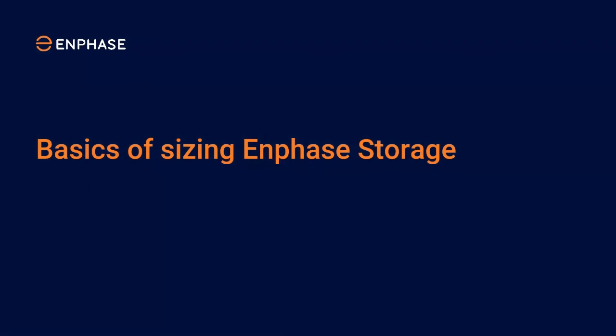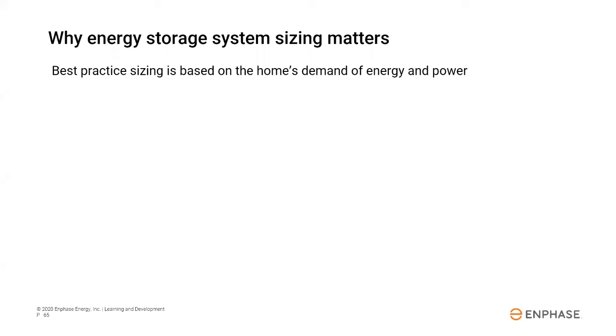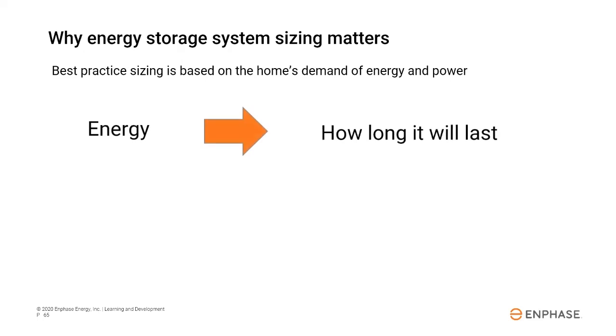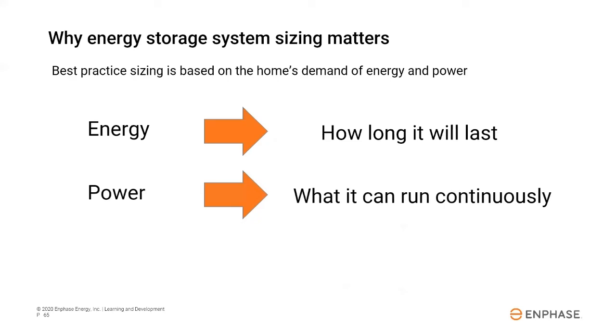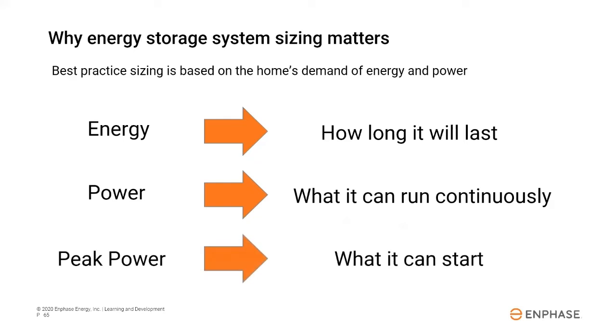Okay, now we're going to talk a little bit about sizing storage. So proper sizing of battery storage for backup power should accomplish 3 goals. First, it ensures that the system has enough energy storage capacity to power the home for the necessary period of time. So energy determines how long it will last. Next, it ensures that the system will have enough power to run the home's loads continuously. And lastly, it ensures that the system has a high enough peak power to start up appliances with high inrush current, like air conditioning and pumps. If your system design achieves all 3 of these, you're going to have a lot of happy customers, a lot of referrals, and very few service calls.